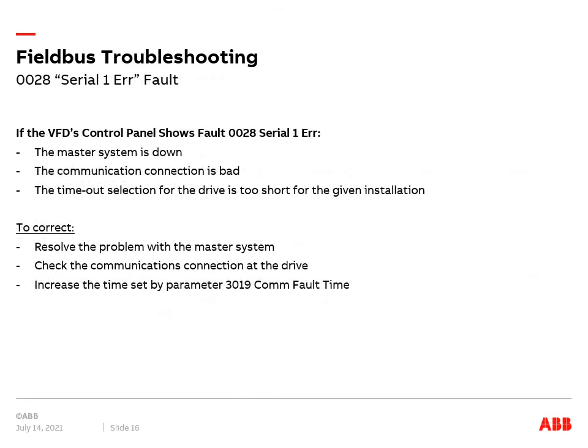Regarding fault 0028 Serial 1 Error, if the VFD's control panel shows this fault, then either the master system is down, the communication connection is bad, or the timeout selection for the drive is too short for the given installation. To correct this problem, resolve the issue with the master system, check the communications connection at the drive, or increase the time set by parameter 3019 COM fault time.